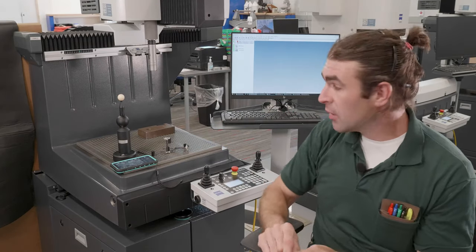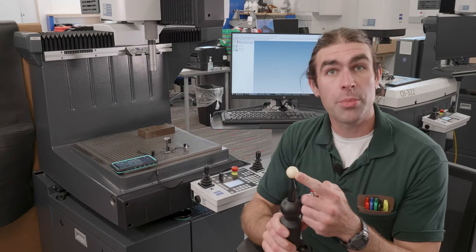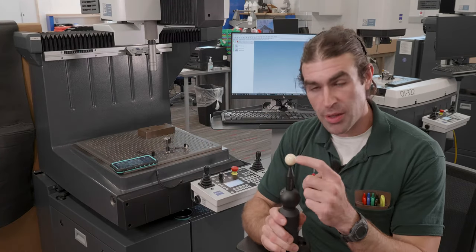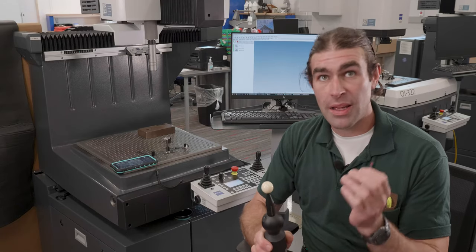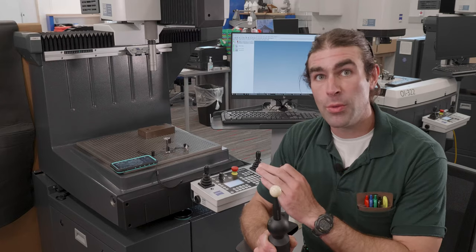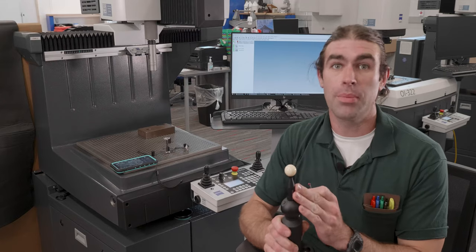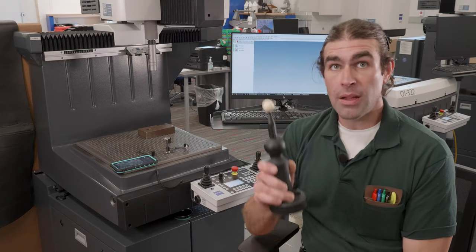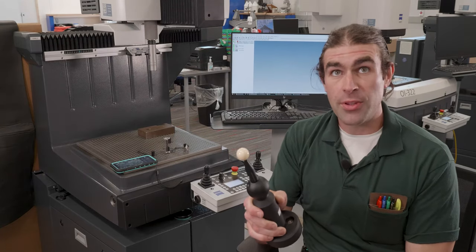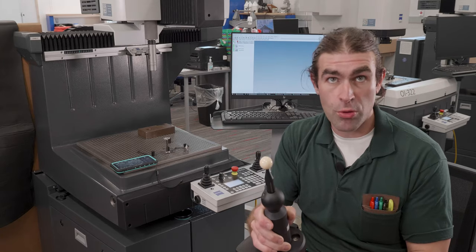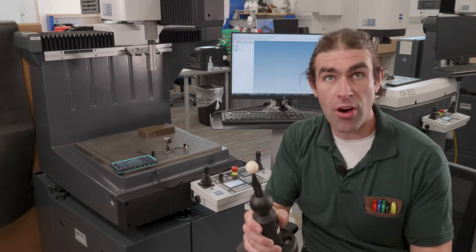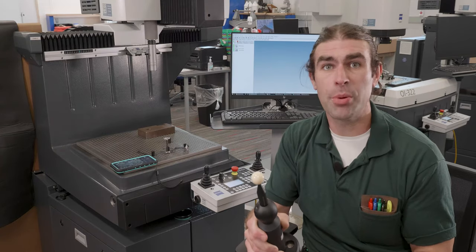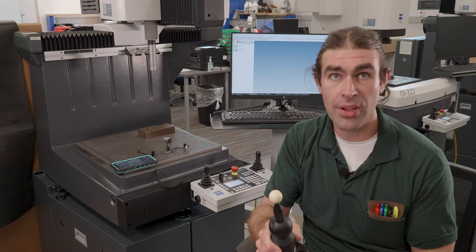So the reference sphere comes from the factory. This ball of rock has a known diameter. It's very accurate and it's matched to the machine. So you don't want to mix these up with machines. You definitely don't want to drop it. In a minute, we'll bolt it down to the machine. You can leave it bolted to the machine. If you have a really big part, you might have to take it off, but you'll have to put it back on if you're going to re-qualify stylus systems.